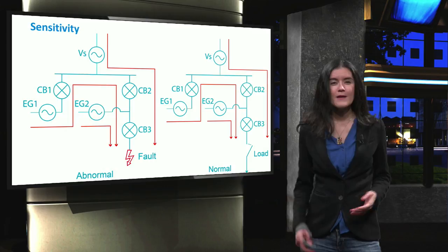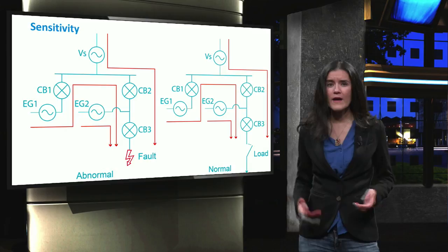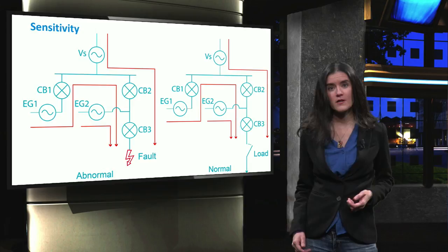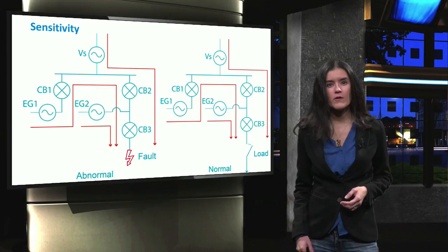Since we don't want the circuit breaker indicated with CB in the drawing to react when the system is in normal conditions, we need to make sure that the protection devices implemented in the network will respond only when a predetermined level of fault current is reached. Too sensitive circuit breakers might trip unexpectedly, causing unnecessary power interruption.